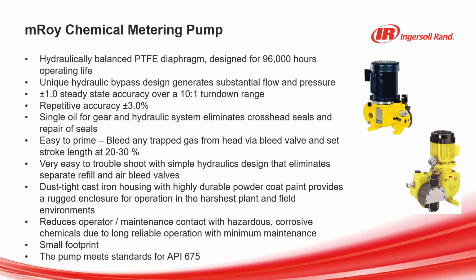The temperature ranges are very wide in these as well, and all MROY pumps include a hydraulically balanced PTFE diaphragm. This is designed for 96,000 hours of operating life. So these pumps are known in the RNG process for being reliable, being long-lasting, and being able to provide consistent results in balancing chemistry, both, again, on the water treatment side and in process of RNG production. You're going to be able to achieve a plus or minus 1% steady state accuracy over a 10 to 1 turn down range. So these are versatile pumps. While they're more industrial, higher flows, and also higher pressures, you're still getting the accuracy and repeatability that you would expect from a chemical metering pump.